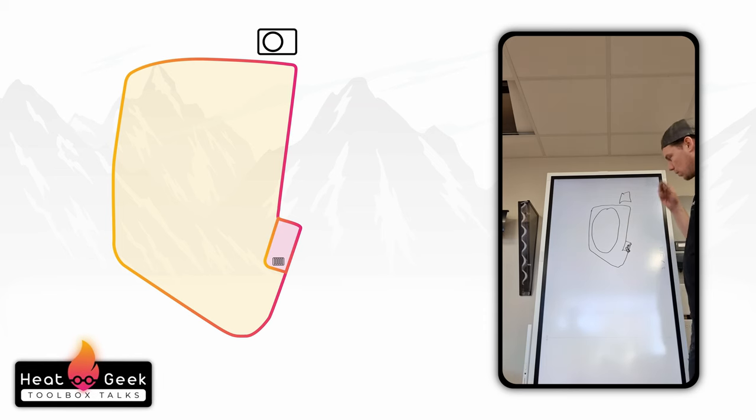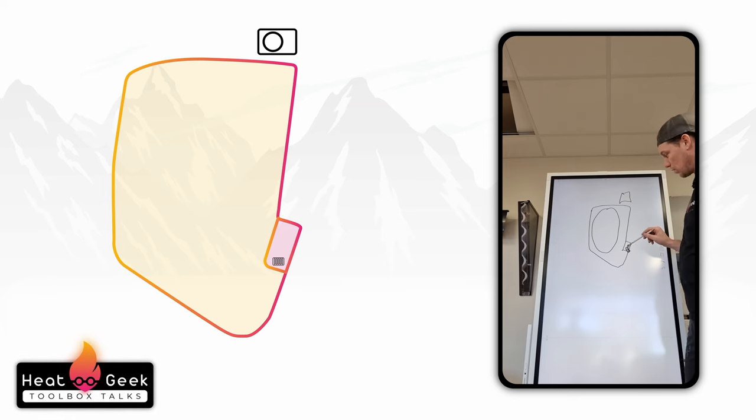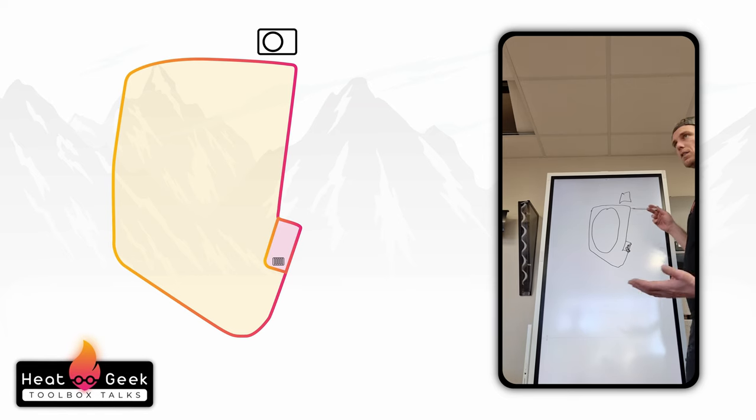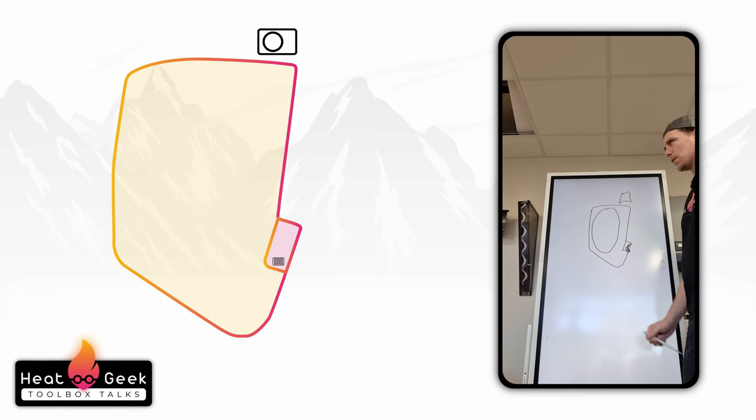It's going through there and it's just gonna cycle, cycle, cycle and it's just gonna lead to breakage. So I just put either a little electric heater or air-to-air or whatever in that one system. So I wouldn't even zone that. I'd zone but with different heat sources in that scenario. So there's not very many places I would zone.